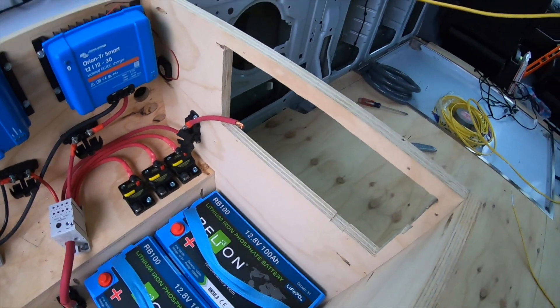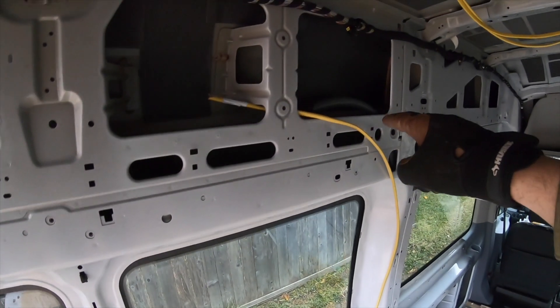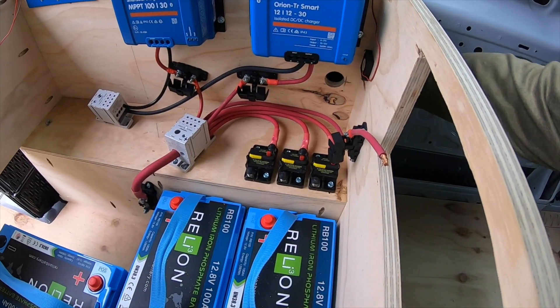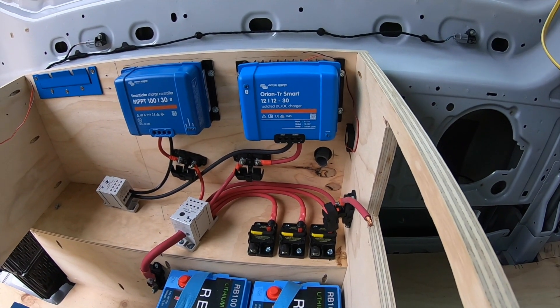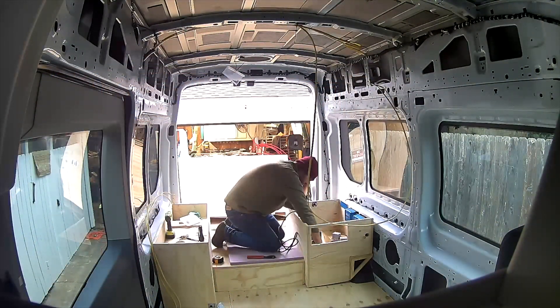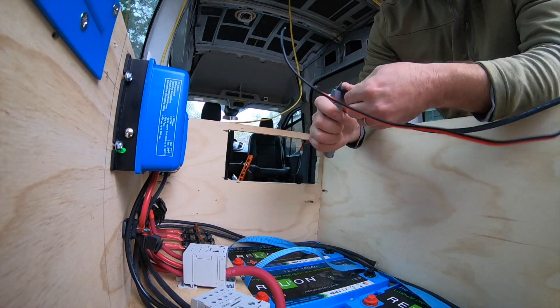Fix this hole — this was where the panel was going to go, but we decided we were actually going to put the panel up there instead in a cabinet. So now we have our ducting that runs down through, ends up back here and into this little hole here, so that guy will pop out. One thing to consider when you are wiring your batteries: the wires from your batteries to your distributors or your bus bar need to be the same length, so that your charge and your discharge are equal across your batteries.